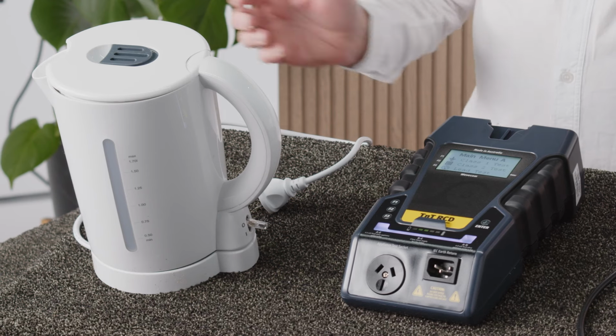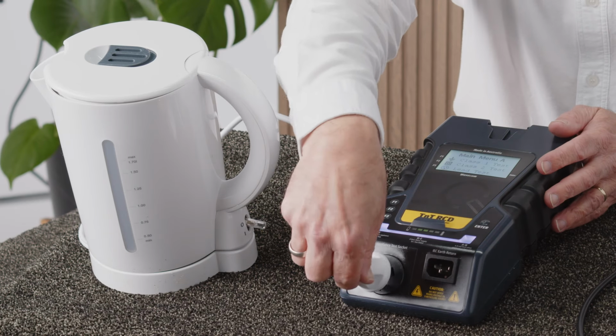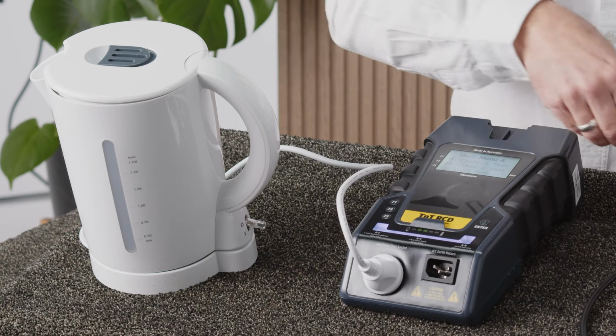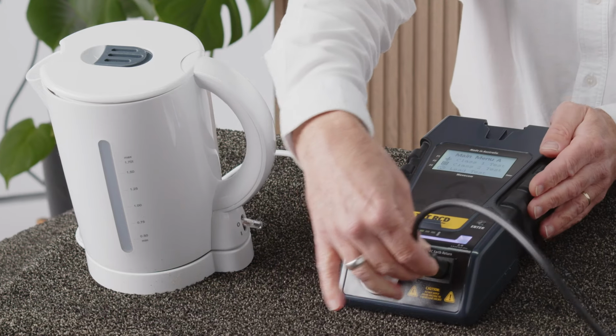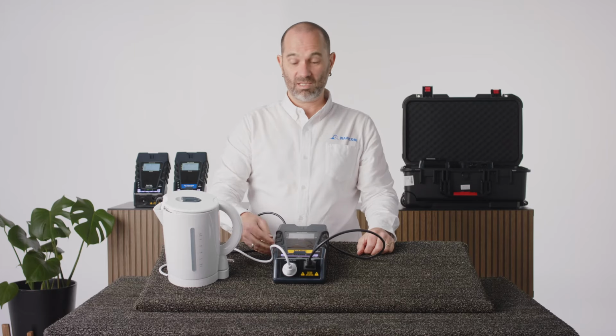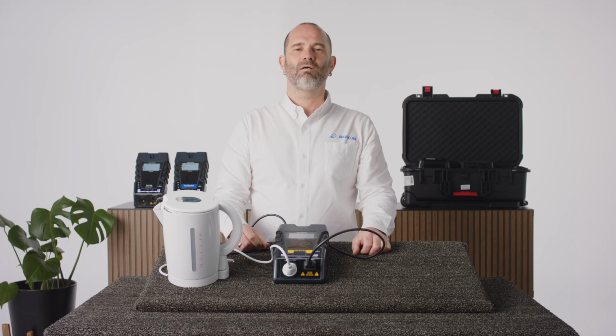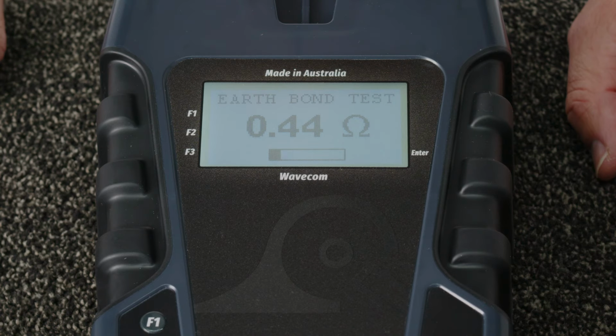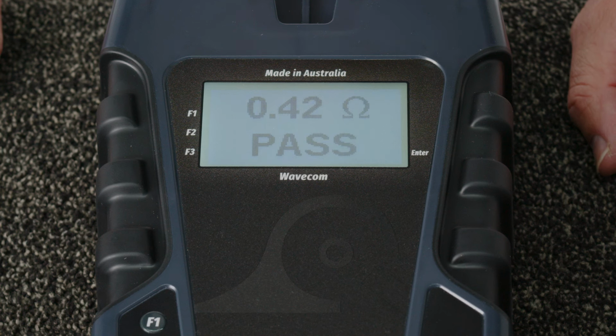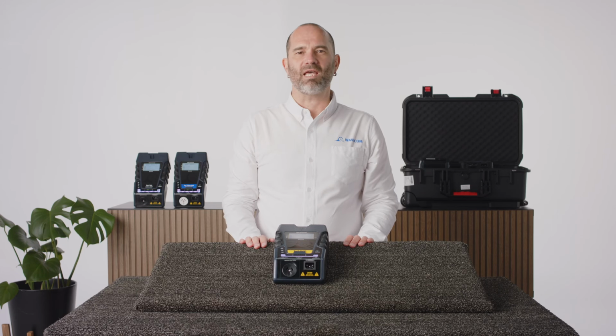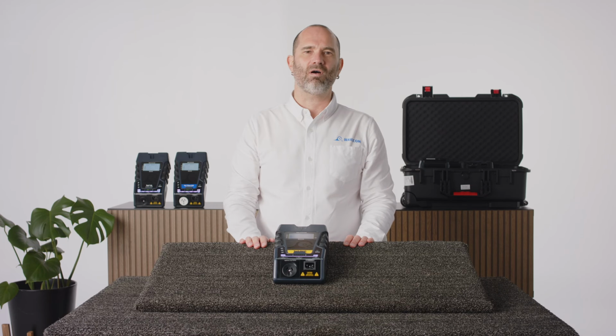test. Testing is as simple as connecting your test leads, and selecting your test. The TnT RCD will run through the different tests required under the standard, showing the various readings on screen, and will give you a pass or fail result. One feature that is really handy is the new RCD testing design. That means that you can test portable RCDs without external isolation transformers or worrying about tripping the mains RCD.